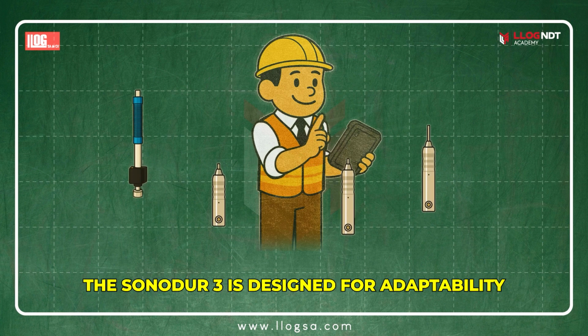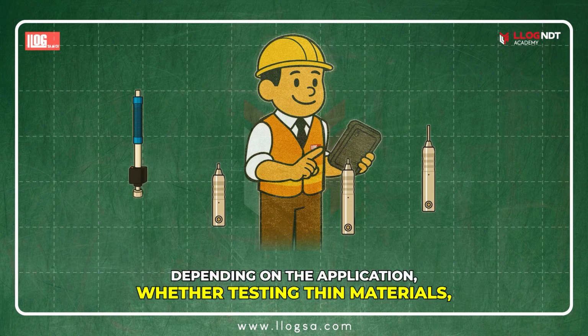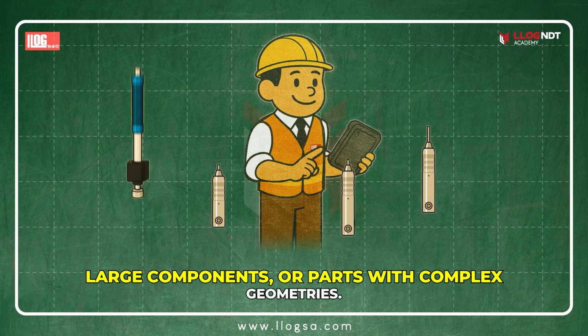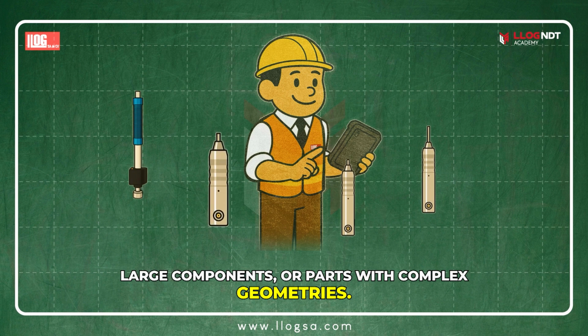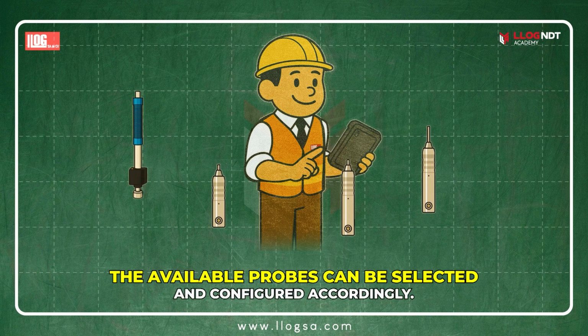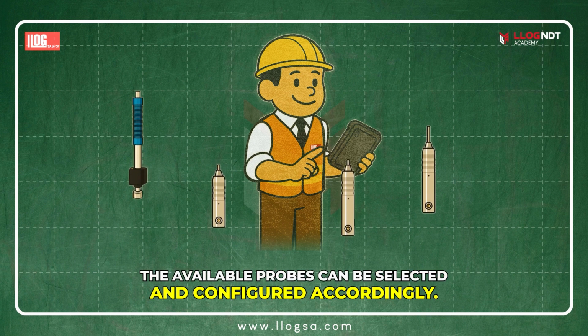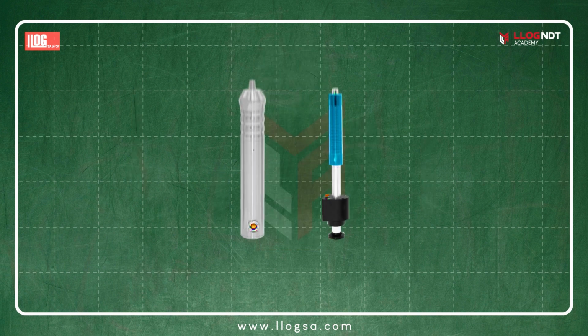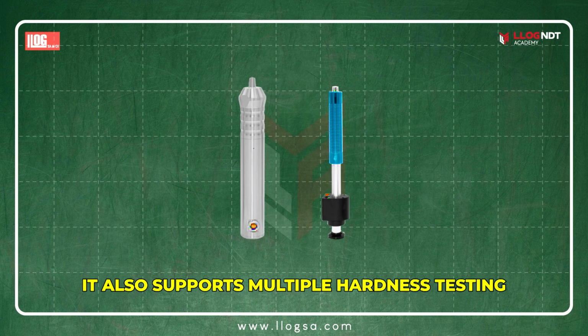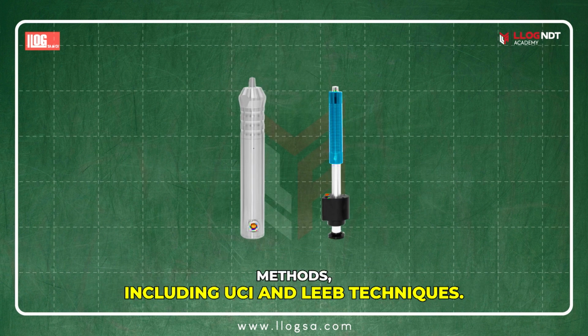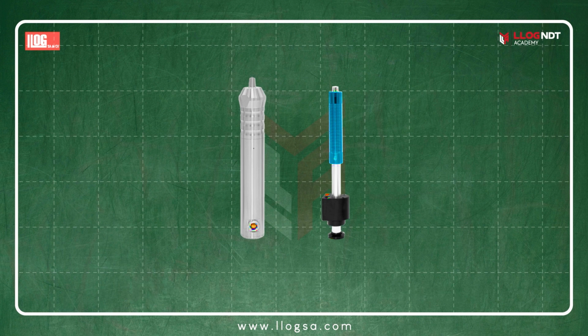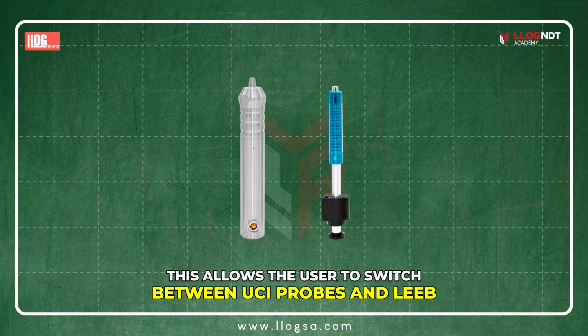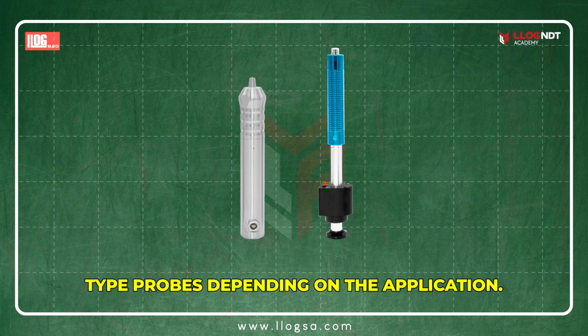The Sonodur 3 is designed for adaptability. Depending on the application, whether testing thin materials, large components, or parts with complex geometries, the available probes can be selected and configured accordingly. It also supports multiple hardness testing methods, including UCI and LEEB techniques. This allows the user to switch between UCI probes and LEEB-type probes, depending on the application.